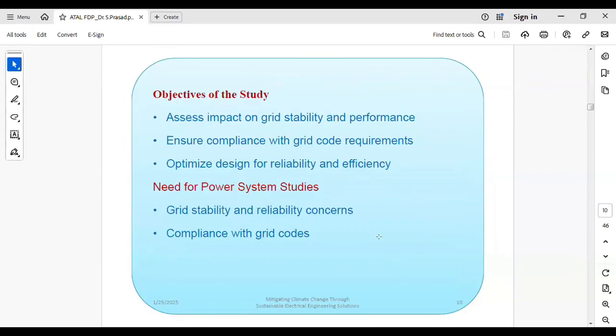The main objective of the study is to assess the impact on grid stability and performance. The system has to be stable. If you are integrating the PV plant to the grid, the grid should not get disturbed. So you have to ensure that the grid will be stable when integrating the PV plant into it. Therefore, we are conducting all these studies, and a report has to be submitted to the grid utilities for approval. Only after getting the approval will we go for first time charging of the PV plant, and ensure compliance with the grid code requirements. As I said, we have to follow the grid codes for different kinds of studies, and ensure that it follows all the grid code rules. And we have to optimize the design for reliability and efficiency, so you have to optimize the PV plant design for its reliable operation.